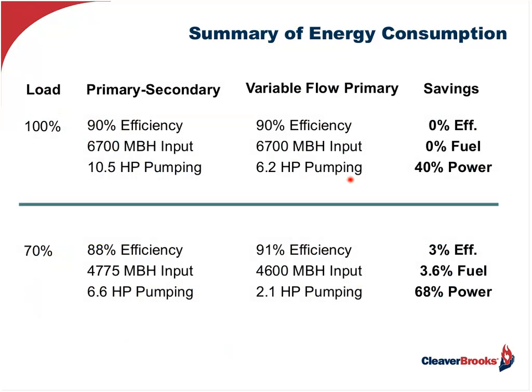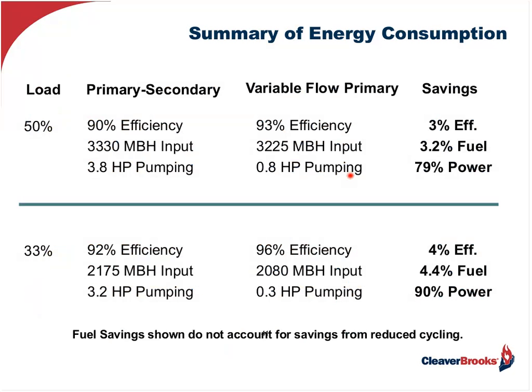At 70% load, you'll see a 3% increase in boiler efficiency, which is going to amount to a 3.6% savings in fuel and a 68% savings in pumping horsepower. At 50% load, you're still going to save roughly 3.2% in fuel, and your pumping horsepower savings go up to 79%. And finally, the lower you get, your fuel savings will go up a little bit more, in this case to 4.4%, but the dramatic increase is 90% less pumping horsepower. So these savings don't include anything from reduced cycling, which you typically have more of with a primary-secondary system.